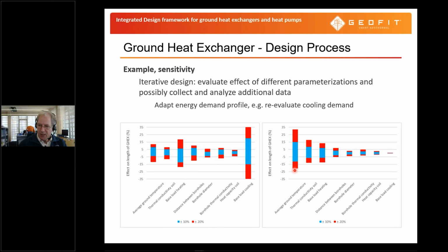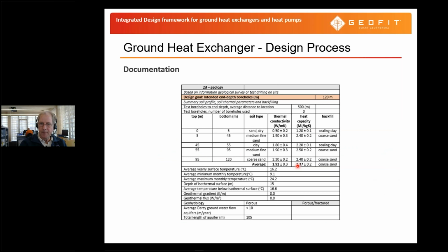In the other example here, we see, for instance, that the average ground temperature can have a large effect. In that case, we could say, okay, if we do a test borehole on site, or we have other data available from the site where we can have a better parameterization, a better estimate of average ground temperature, that would be a good idea. And then finally, we want to document the design. So in the design report that we've generated, we have all these tables where the actual design and the choices that have been made can be clearly documented.